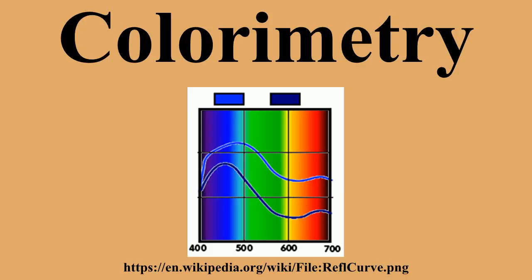These readings are typically used to draw the sample's spectral reflectance curve, the most accurate data that can be provided regarding its characteristics. The readings by themselves are typically not as useful as the tristimulus values, which can be converted into chromaticity coordinates and manipulated through color space transformations. For this purpose, a spectrocolorimeter may be used. A spectrocolorimeter is simply a spectrophotometer that can estimate tristimulus values by numerical integration.